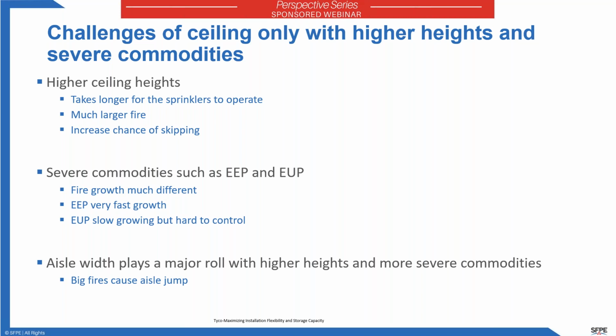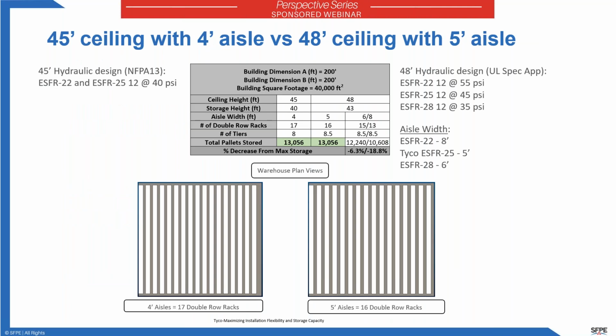of aisle jump. Aisle jump occurs when the fire from the main array jumps across the aisle and ignites the target arrays in these fire tests. So all of these contribute to making it much more challenging to get ceiling-only fire protection at higher ceiling heights. So, as I mentioned, there are sprinklers approved at a 48-foot ceiling, the specific application listing. So this chart compares the amount of storage you can have at the different ceiling heights and different storage heights between a 48-foot ceiling with 43 feet of storage and a 45-foot ceiling with 40 feet of storage.